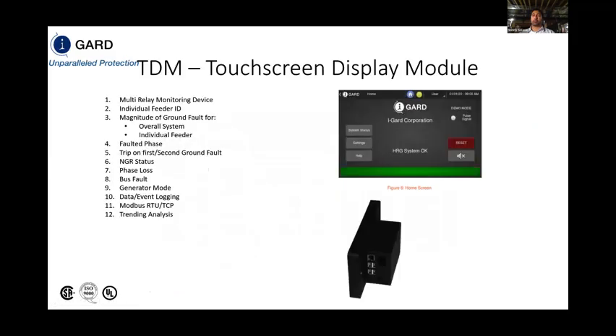And here is the modular solution that we've provided to our customers for many years. We have our arc flash detection module on the right, our main tie main module. We have feeder modules, resistor monitoring relay, our DSM, which monitors the voltages between the phases as well as to ground, as well as the neutral voltage. We have our power supply here, which controls the pulsing signal for the resistor for fault location, as well as powering all of these modules that are hooked up by ribbon cables between each other. All of this information is connected to our communication module, which sets up to this nice touchscreen display.